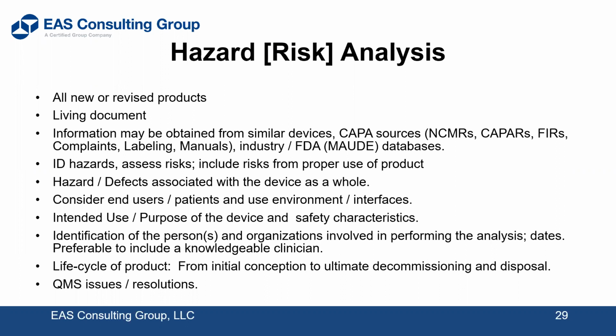I'll show you how. Those of you that are purists that object to a failure mode, including normal, have a separate one. Have a normal effect analysis, or a list structured to address the same kind of concerns that you have in your FMEA and FMECA, but address it some way. That, to me, eliminates the issues that the field has about the use of a failure mode effect analysis in this procedure. But bear in mind, in the older versions of 14971, FMEA or FMECA was called out as an acceptable tool. And I've never had a regulatory agency question me on the use of it. Nor have I had them question me on my inclusion of normal in the use of those tools. But that's up to you how you do it, but do address normal.